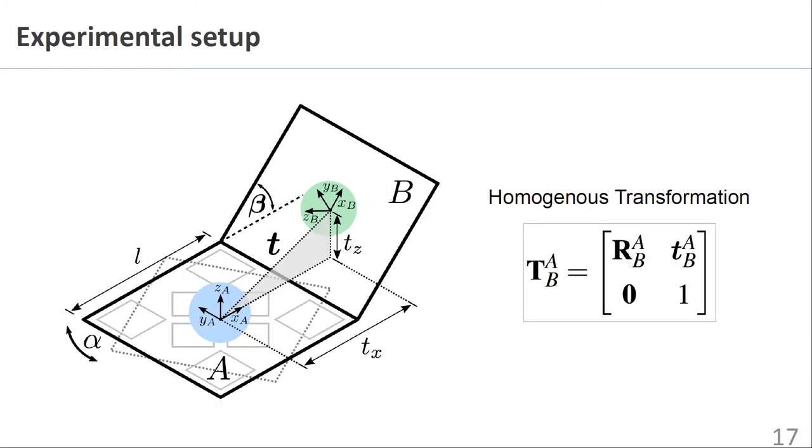This design allows for field generators to be tilted with respect to one another. In this example, field generator A shares a common edge with field generator B. The angle alpha represents the rotation of field generator A about its z-axis, which is 0 degrees in this case. The tilt of field generator B is shown as beta. Given that the dimensions of the field generators are known and the tilt angle beta is also known, then the location of field generator B can be described by a single homogenous transformation matrix, where R is the rotation matrix, and little t is the displacement between the origins of field generator A and field generator B.